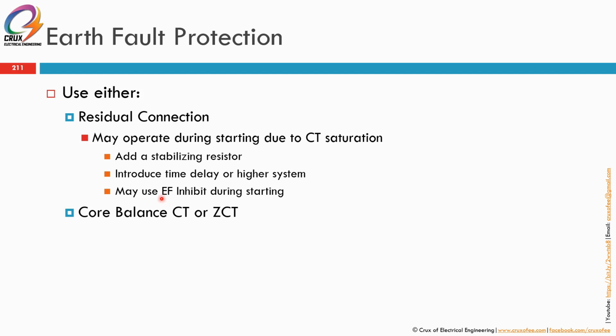inhibit the earth fault. For example, as long as the current is more than 2 times the full load current, inhibit the earth fault. So this one depends on the type of relay that you are using lah. The easiest is just to add a stabilizing resistor lah. So basically when you add the stabilizing resistor, you are actually decreasing the sensitivity of the earth fault relay lah. Okay, the second type is core balance CT or ZCT lah.